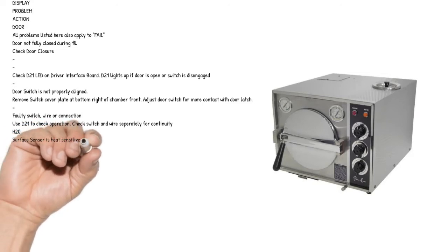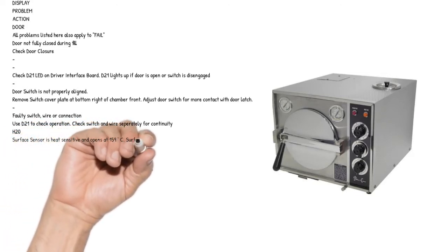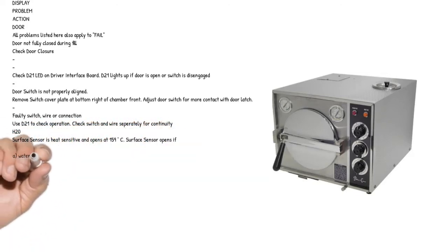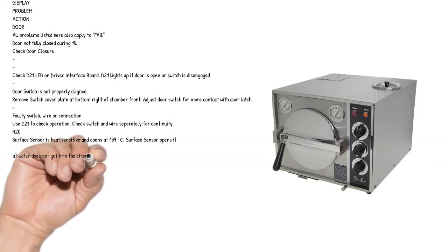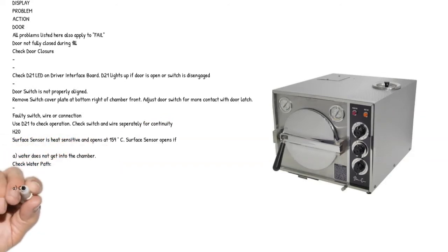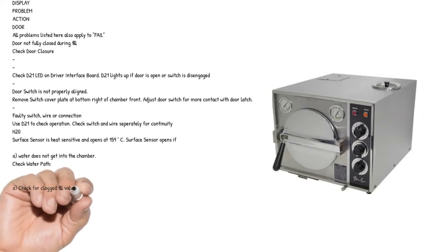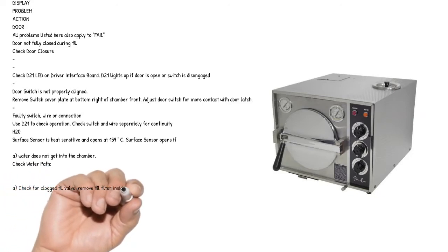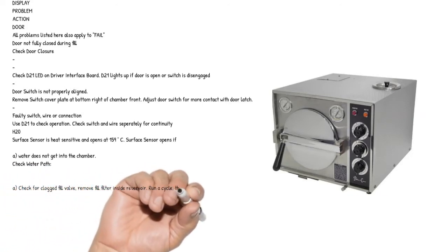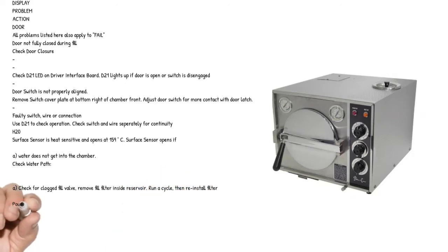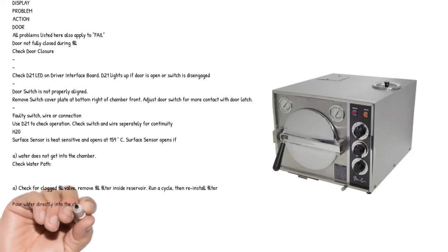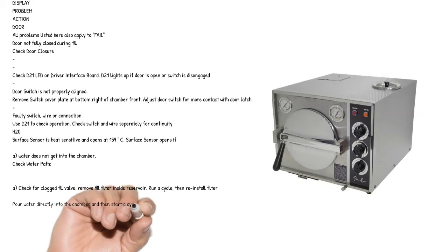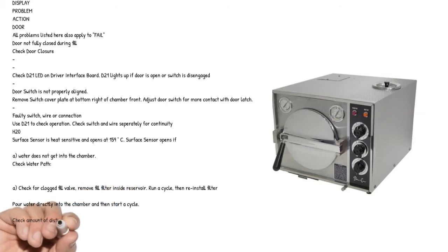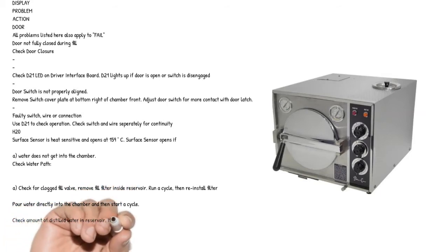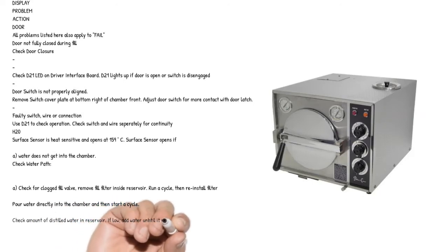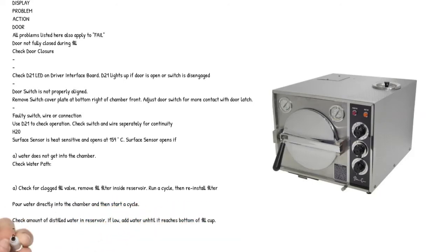H2O. Surface sensor is heat sensitive and opens at 159 degrees Celsius. Surface sensor opens if A. Water does not get into the chamber. Check water path. A. Check for clogged fill valve, remove fill filter inside reservoir. Run a cycle, then reinstall filter. Pour water directly into the chamber and then start a cycle. Check amount of distilled water in reservoir. If low, add water until it reaches bottom of fill cup.